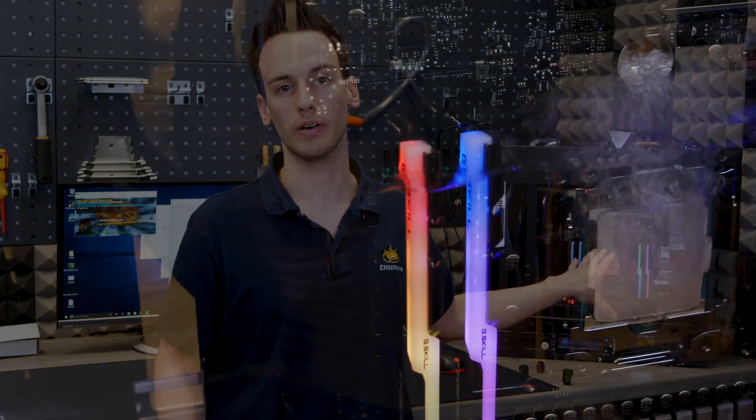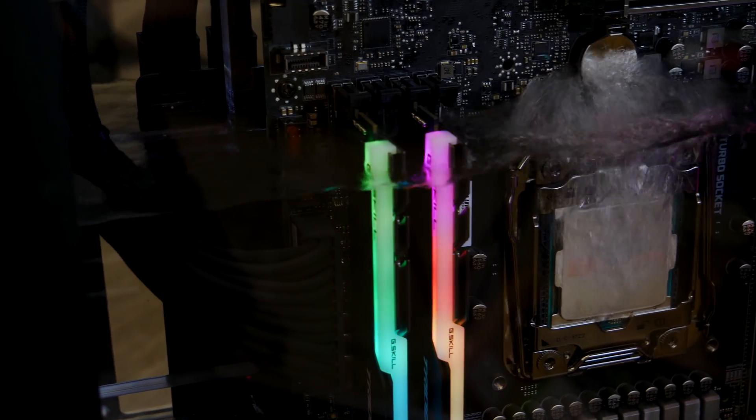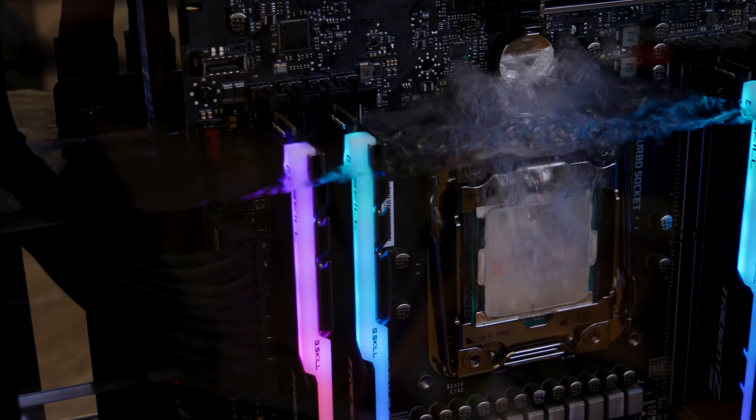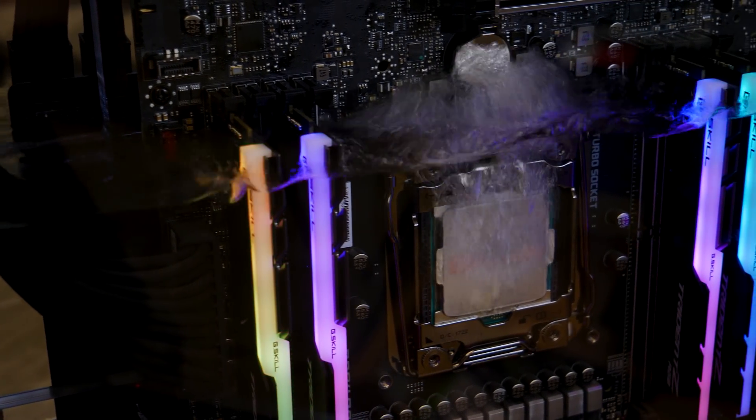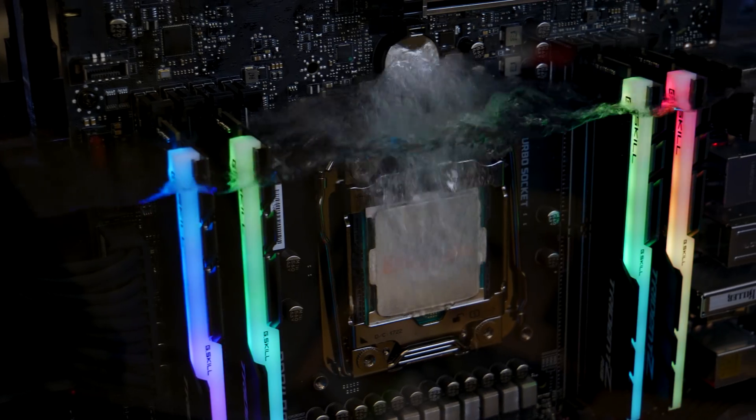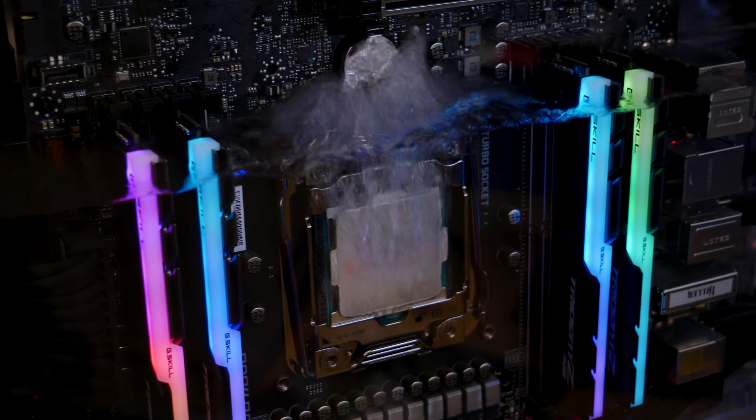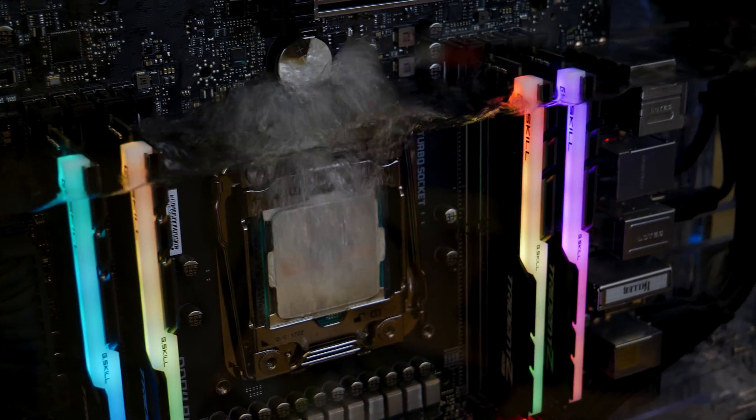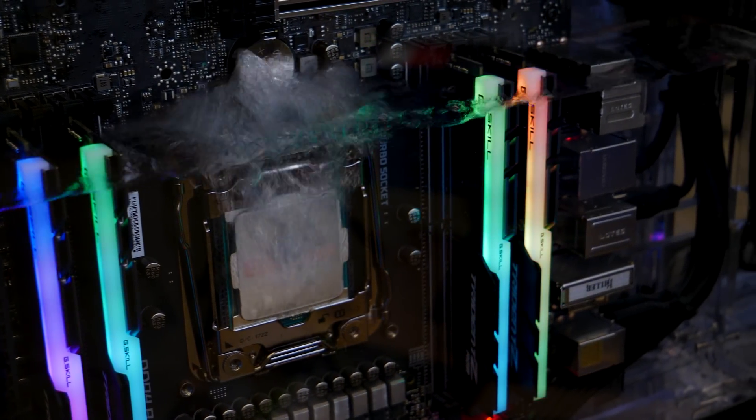In this case, we don't have this problem because we want the fluid to evaporate. That's why we're using 3M Novec 7100, because the boiling point is fairly low. We have a boiling point of 61 degrees Celsius, which is still suitable for all the hardware inside. Of course, the fluid is not electrically conductive. It's also not reactive, so we don't have any issues with any components inside.